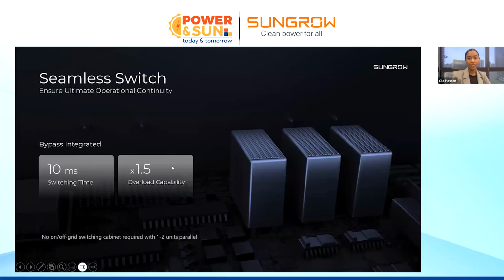Also, seamless switching. So if the grid goes off or there's load shedding that happens suddenly, the inverter takes 10 milliseconds to switch from on-grid to off-grid. And also it has 1.5 overloading capacity for the first 10 seconds. Overloading capacity is actually used when we have an off-grid application. For example, let's say the grid is not there and my system is carrying the full load, but some of the loads have very high starting current at the beginning. So the inverter can provide you with 50% additional overloading capacity for the first 10 seconds to support these high current loads at the starting point, and then it goes back to its normal operation mode.